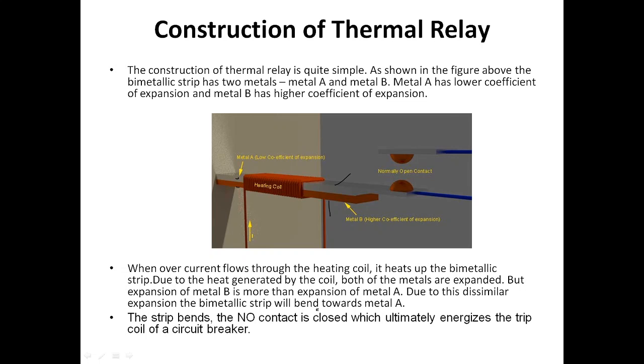When overcurrent flows through the heating coil, this one is the heating coil, it heats up the bimetallic strip. Due to the heat generated by the coil, both of the metals expand, but the expansion of metal B is more than the expansion of metal A. Due to this dissimilar expansion, the bimetallic strip is bent towards metal A. The strip bends. The normally open contact is closed, which ultimately energizes the trip coil of a circuit breaker.